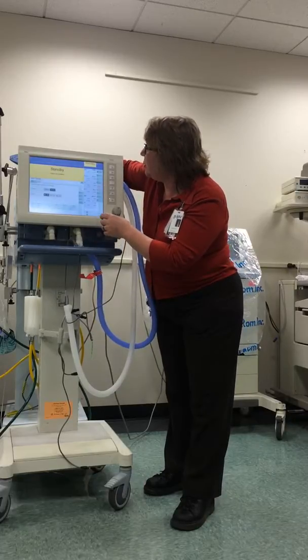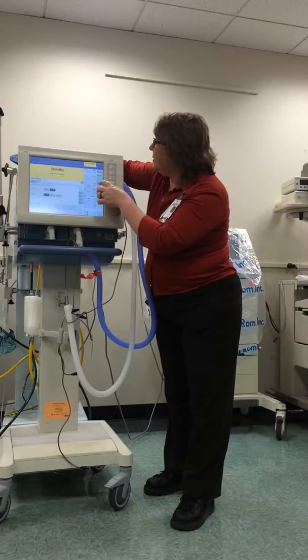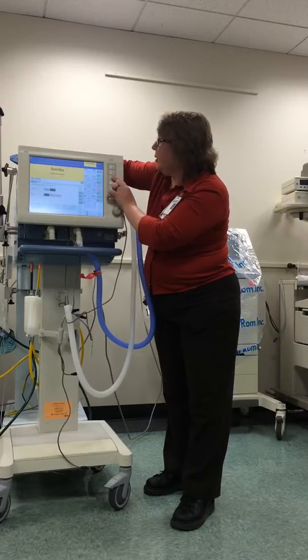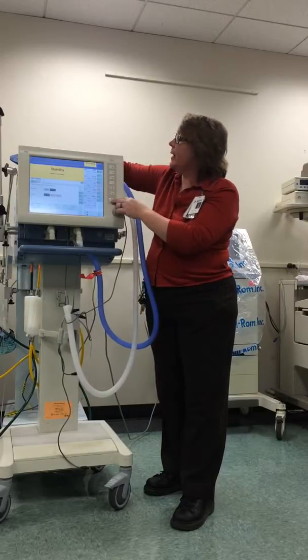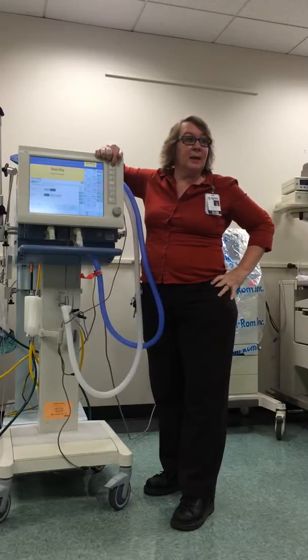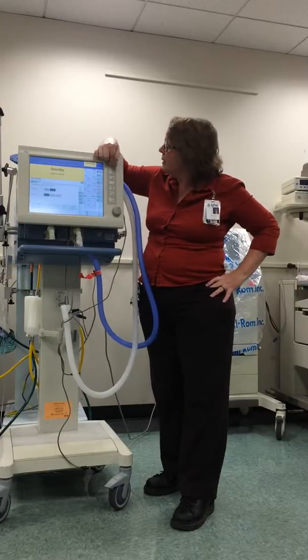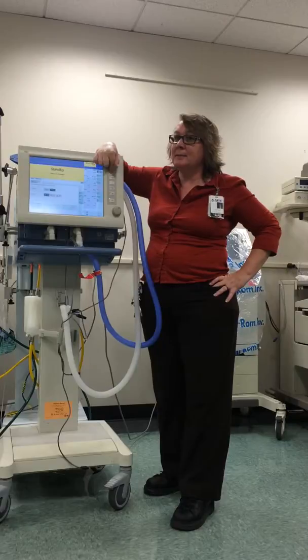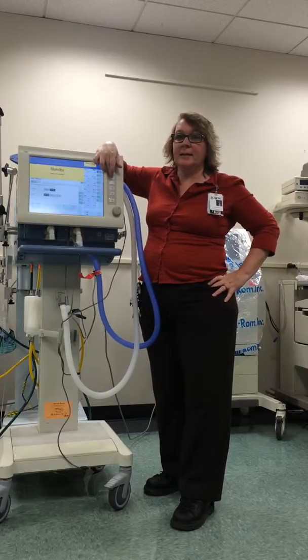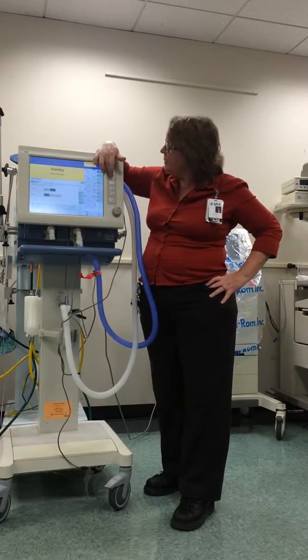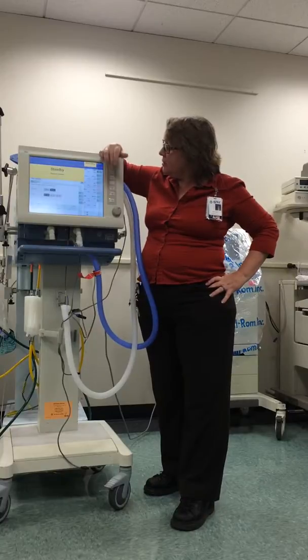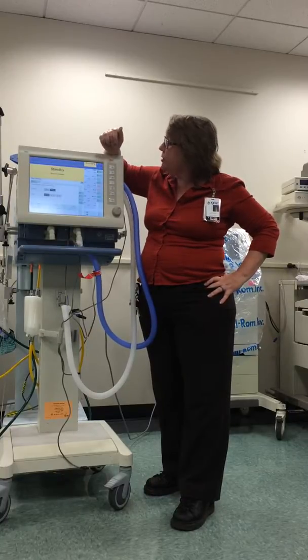If I want to, I can set some settings right now. We could go to here, over here on the right-hand side. Top button is my alarm silence. Next one are my alarm limits. Ventilator settings, that's where I can actually set everything. Sensor parameters I'll get to, and system setup I'll get to.